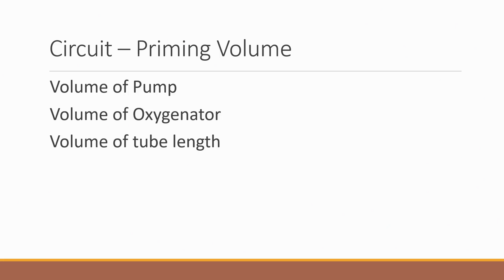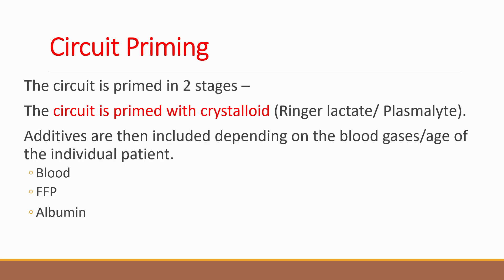So when you are preparing the circuit on your own, you have to see the size of the tube you are going to use, the size of the oxygenator, and the pump you are going to use. All of that is important. And how will you choose the oxygenator size? Depending upon how much total flow you will require and how long you need to use the oxygenator. Suppose you need the oxygenator for less than 4 to 6 hours, a polypropylene oxygenator is good enough. You don't need to go further, because the cost of polypropylene is 18,000 as compared to 1 lakh for a PMP oxygenator.